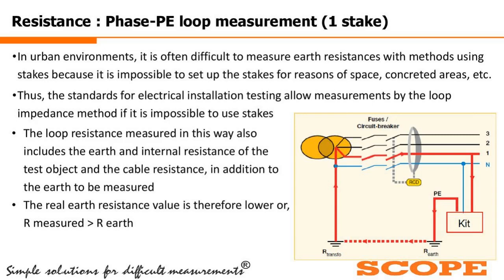So whatever measured value I get, even if I have switched everything off, something or other will give a parallel path. 99% of the time I will get a parallel path, because we cannot stop or physically isolate everything. So R measured, the resistance measured, will be greater than the actual earth resistance, because it is the actual earth resistance value plus the value of the test leads, the value of the rest of the circuit, or whatever else is in the electrical circuit. That resistance gets added over and above the earth resistance.